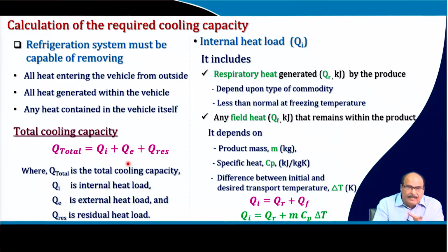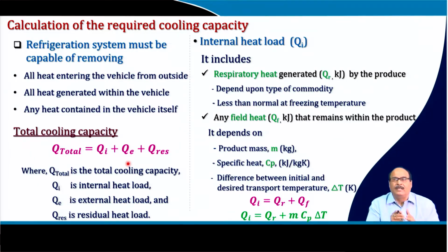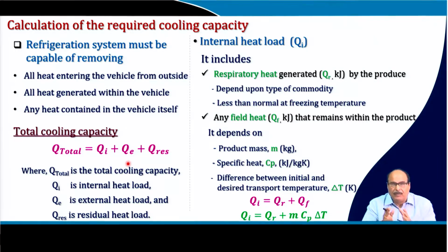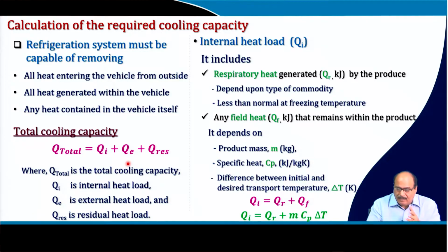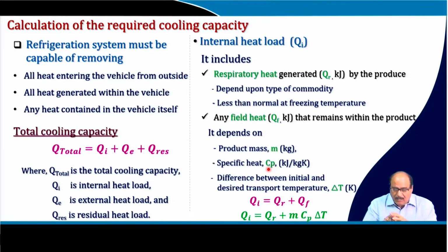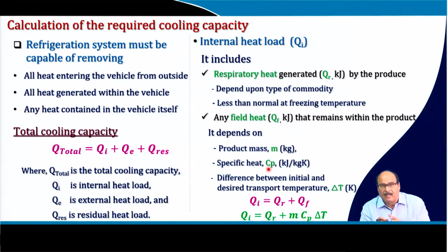Qi is the internal heat load, Qe is the external heat load, and Qres is the residual heat load. Internal heat load Qi includes, as I told you, respiratory heat, that is Qr, generated by the produce. It depends upon the type of the commodity and its loading pattern, and it is generally less than normal at freezing temperatures. Then any field heat, that is Qf, that remains within the product. The field heat Qf depends on the product mass M in kg, specific heat Cp, and the difference between the initial and desired temperature, that is delta T.